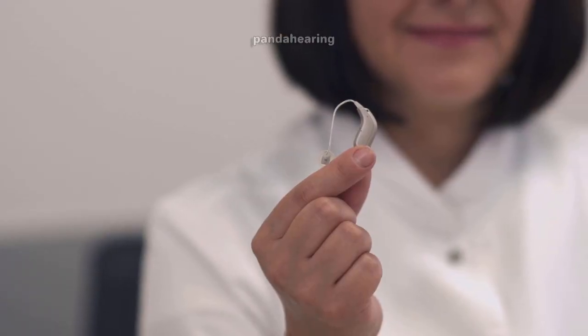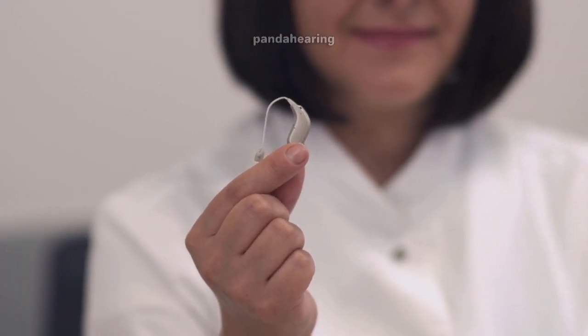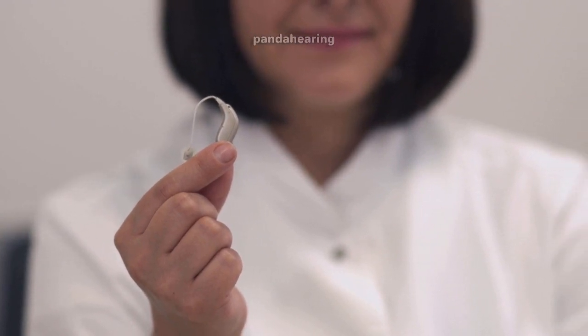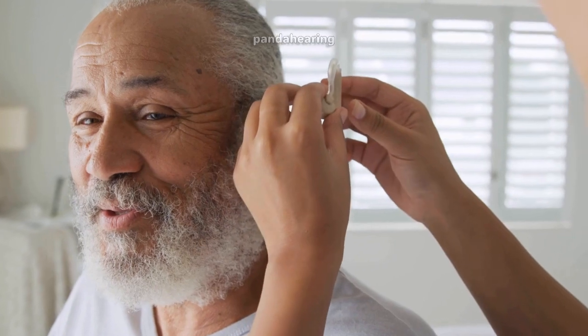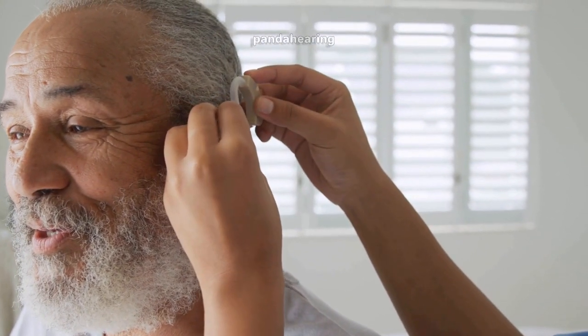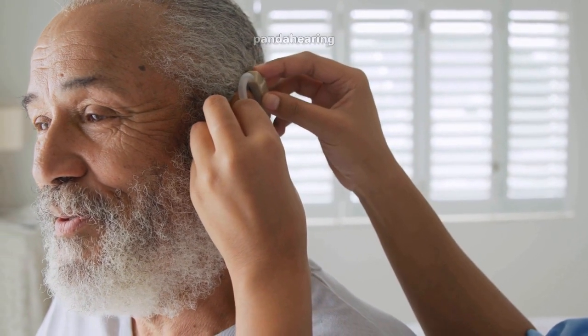A significant accumulation of wax. When there is an accumulation of wax in the ear, the sound that is being amplified by the hearing aid may reflect off of the wax and into the microphone, causing feedback. Concerns about the technology. In certain instances, feedback might be the result of a broken or malfunctioning hearing aid. For instance, if the tubing of the hearing aid is damaged in any way, for example, if it is cracked or has a hole, this might allow sound to seep out and be picked up by the microphone. Several shifts in position. Certain motions, such as giving someone a hug or resting down on a pillow, might produce momentary changes in the way the hearing aid fits, which may result in feedback.